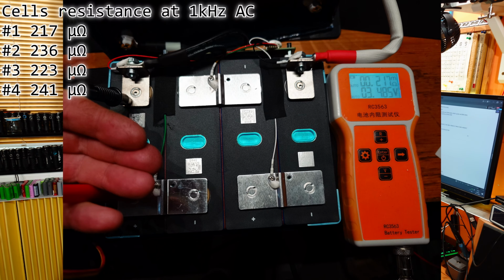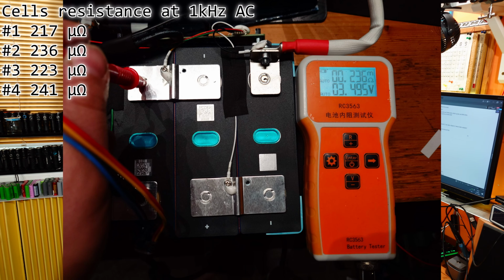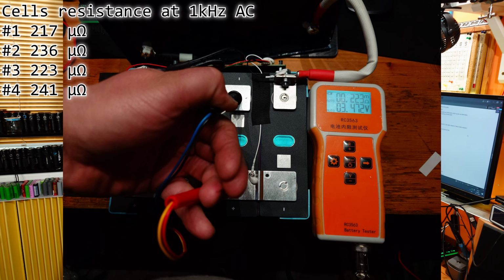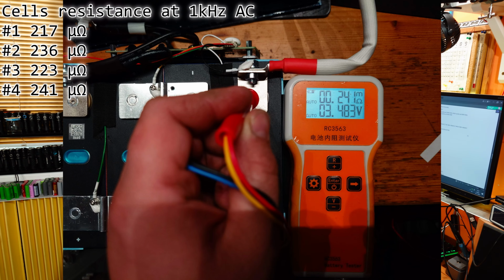Next test was the internal resistance of the cells inside. DC loading resistance testing is generally more accurate as it provides more reliable data, but LiFePO4 cells are not consistent across their charge gradient or over time. So I've resorted to publishing standard AC 1 kHz testing results, shown here on screen. These Gotion cells are good quality, but they lack consistency in their spread of internal resistances, which in this case is approximately 10.4%. The values range from 217 up to 241 microohms, or approximately 0.2 milliohms.